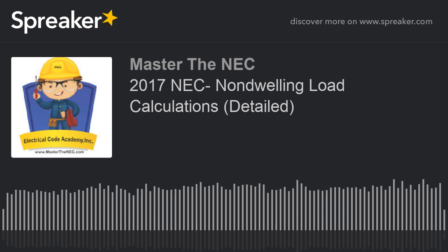Okay, now what about that bank and that store we just did? Those values that we did, $29,750 for the bank and $90,000 for the store, yes, that would be a continuous load. So I want to make sure I put a little asterisk beside that because we're going to take that value in step 5 and add it to our step when we get to the continuous load. You get me? Just put a little mark there. Okay? Don't change the VA values yet. Just put that mark. That's all we want. Okay. Move on to the next stage.